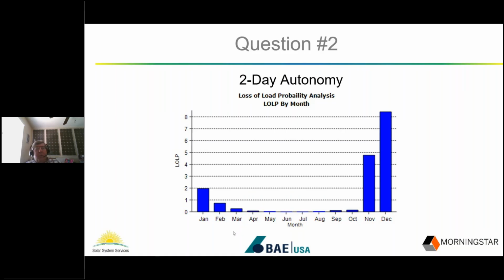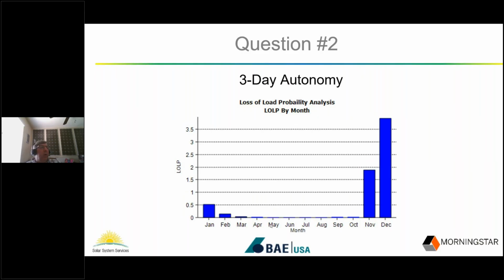At 3 days, you're approaching something workable — about 4% failure in December and 2% in November. For a lighting system or non-critical load, this might be okay if you don't mind it failing a couple of days in December. But I would never do anything less than 3 days, and only if you're okay with occasional downtime.